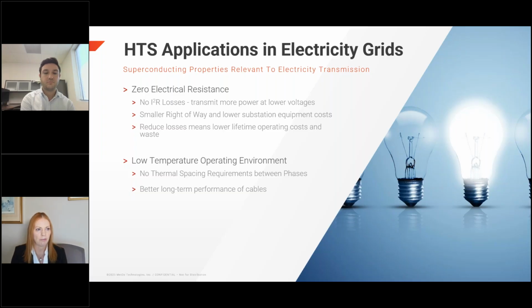If you think about installing a 3-phase cable today, you'd be used to seeing the cables separated by a certain distance, mostly due to thermal dissipation. With HTS cables, you don't have to worry about that. So not only are you installing a lower voltage cable, but you can also install them in a much more compact design. These two benefits really allow us to dramatically reduce the right-of-way required. And we all know that installing high voltage equipment and lines today is very challenging from a siting, permitting, and public acceptance perspective. So reducing and narrowing these rights of way has a lot of benefits.